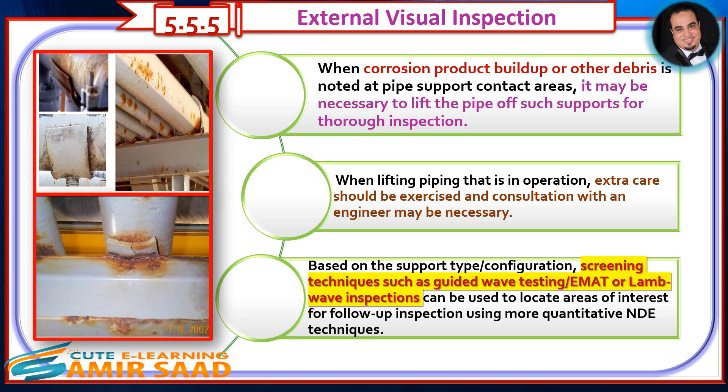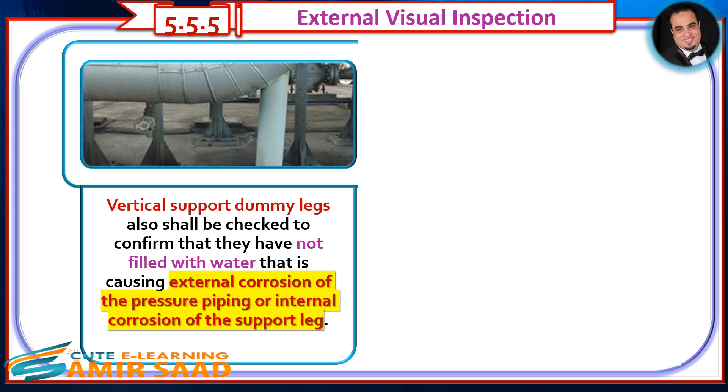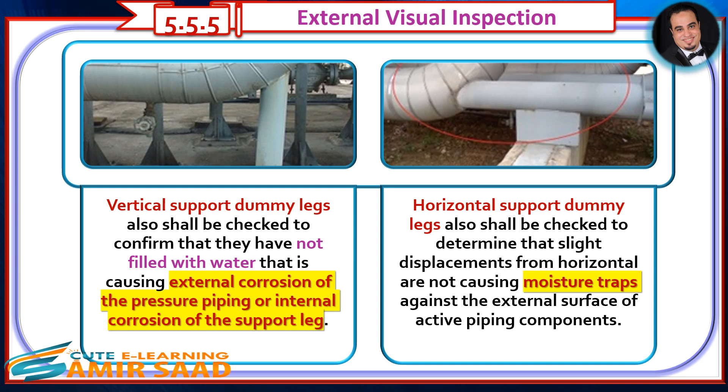Based on the support type and configuration, screening techniques such as guided wave testing, EMAT, or Lamb wave inspections can be used to locate areas of interest for follow-up inspection using more quantitative NDE techniques. Vertical support dummy legs shall be checked to confirm they have not filled with water causing external corrosion of pressure piping or internal corrosion of the support leg. Horizontal support dummy legs shall also be checked to determine that slight displacements from horizontal are not causing moisture traps against the external surface of active piping components.